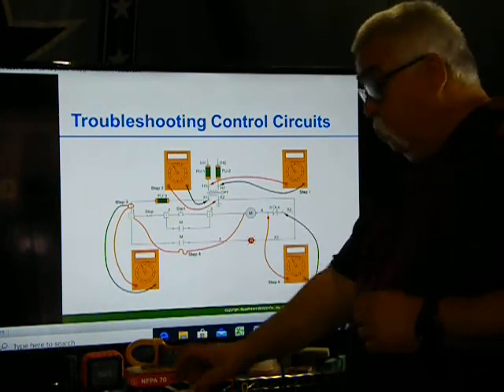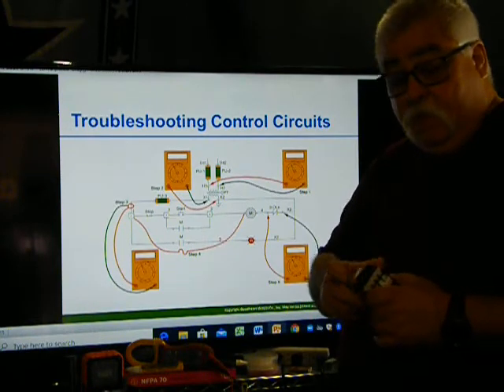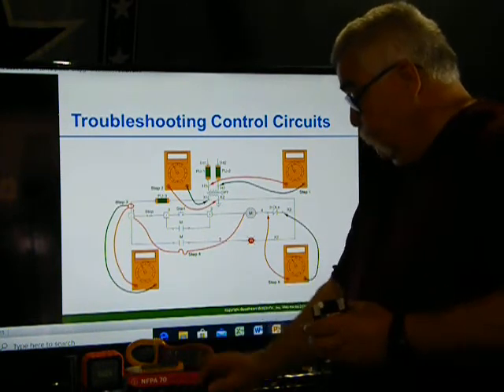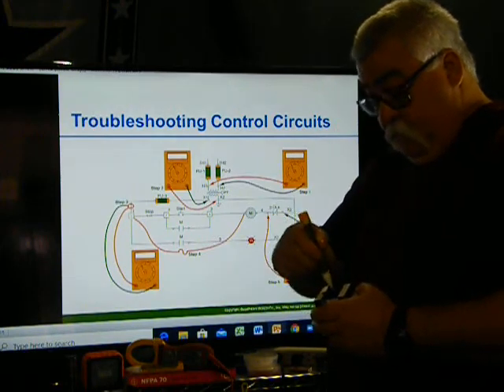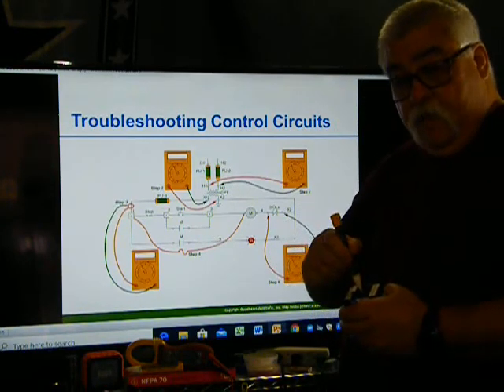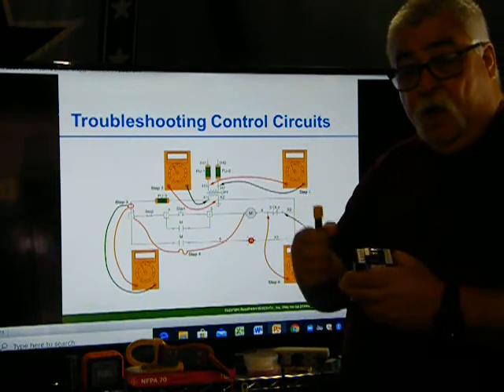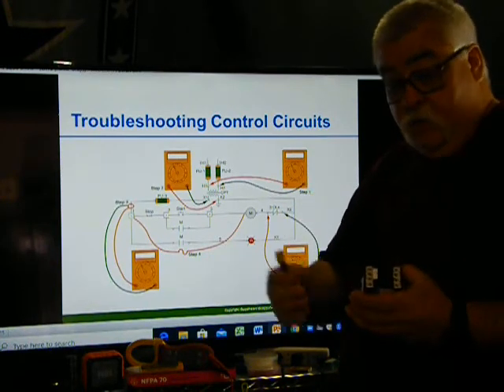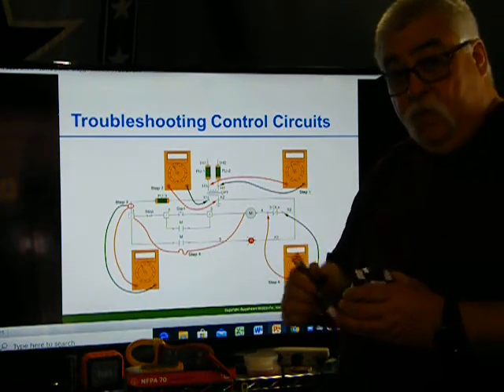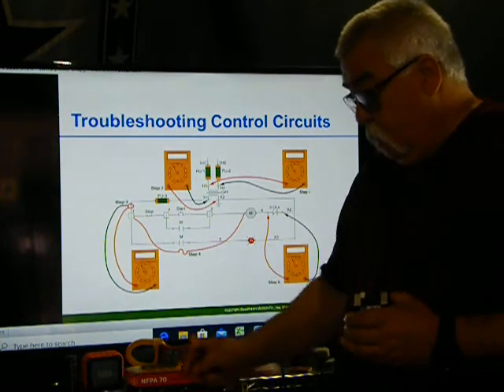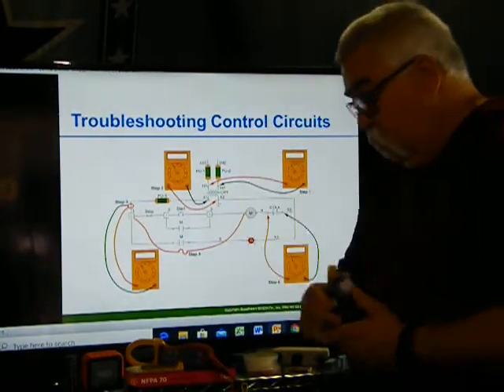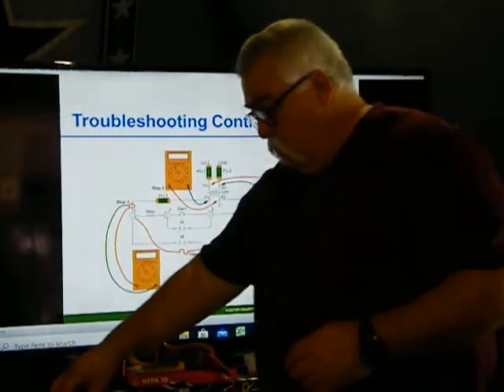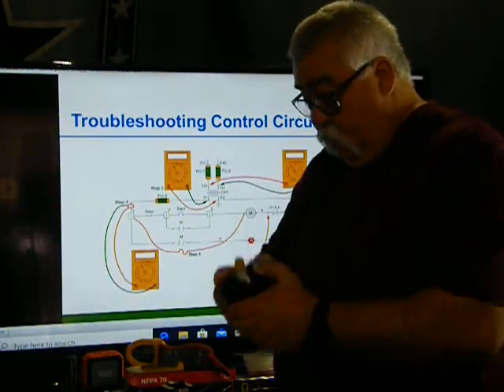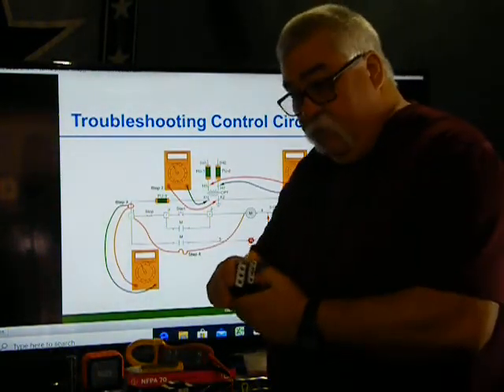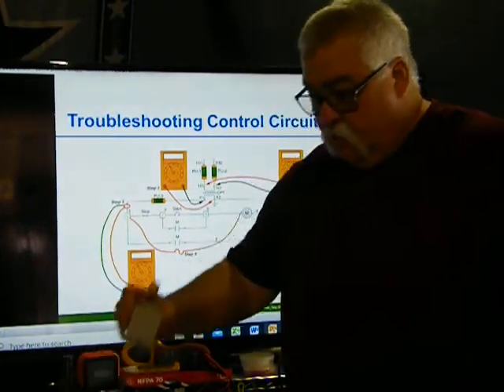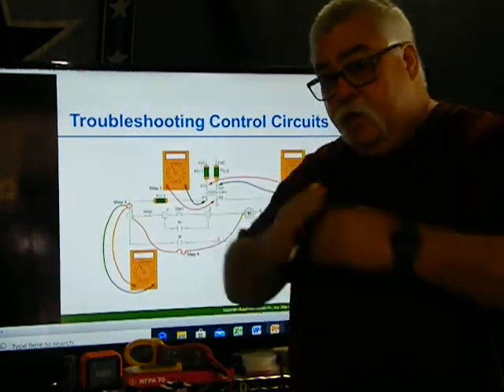If the coil closes, if I get my screwdriver or whatever I may get, push this in, and the motor turns on, then obviously I got a problem somewhere else, because power is going to it. Okay, so it might be the stop-start switches. The contactors may have blown out. The contactors on this might have gone out. Another thing is your overload relay might have tripped and you forgot to reset it. You know, it could be one of the relays that's not closing and holding.